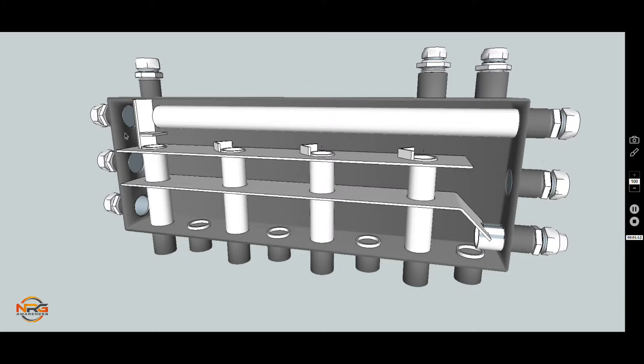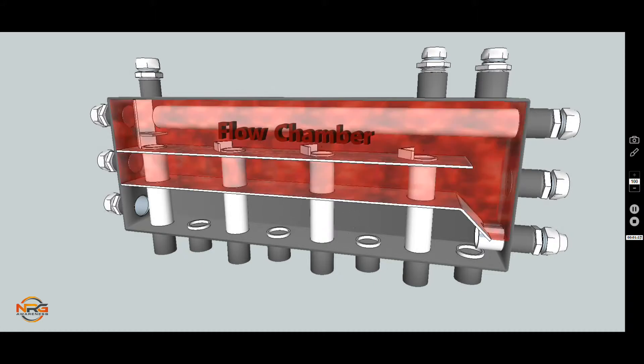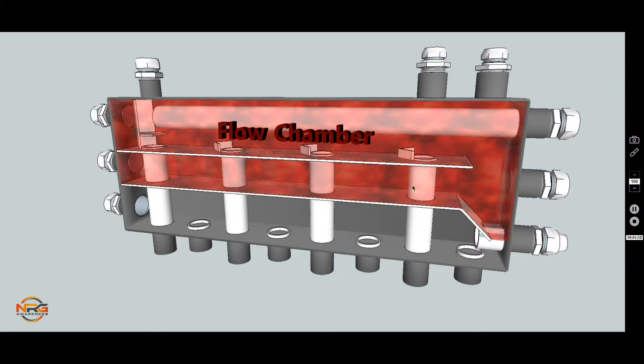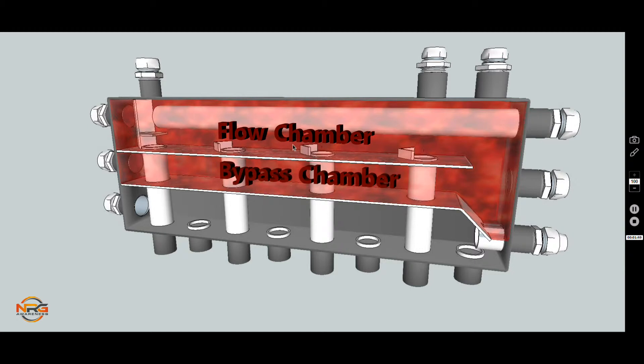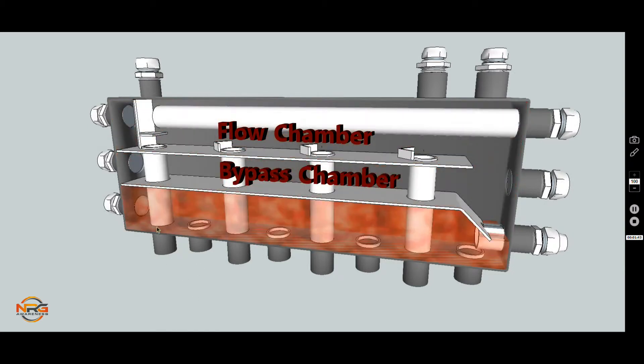If the zones are working and cold water is coming back because the radiators or underfloor circuit is drawing the energy away, then the water would arrive down to the lowest chamber. Inside, in the top chamber, when heat is being delivered in, it collects any heat as it passes through, so hot water is available for the zones to operate. But if the returns are working because the zones are calling, then the coldest water in the system will be collected in this chamber and that would be offered back to condensing boilers or heat pumps.